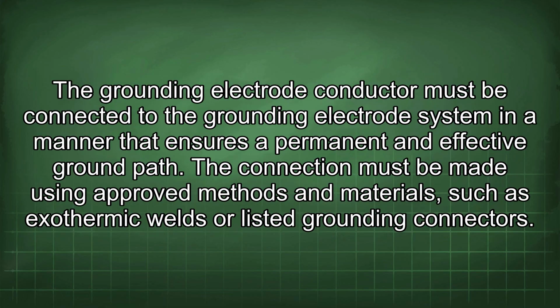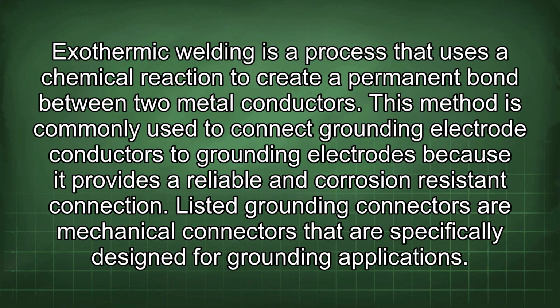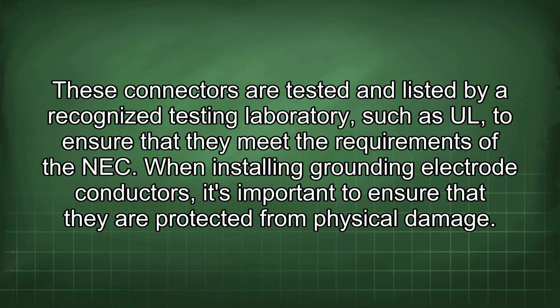The grounding electrode conductor must be connected to the grounding electrode system in a manner that ensures a permanent and effective ground path. The connection must be made using approved methods and materials such as exothermic welds or listed grounding connectors. Exothermic welding is a process that uses a chemical reaction to create a permanent bond between two metal conductors. This method is commonly used to connect grounding electrode conductors to grounding electrodes because it provides a reliable and corrosion-resistant connection. Listed grounding connectors are mechanical connectors that are specifically designed for grounding applications. These connectors are tested and listed by a recognized testing laboratory such as UL to ensure that they meet the requirements of the NEC.